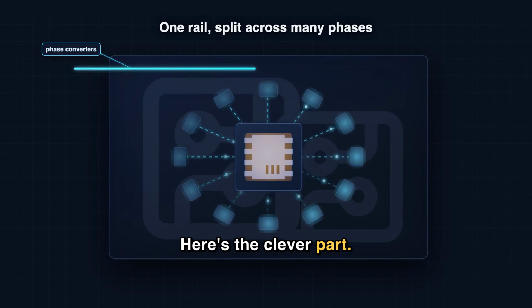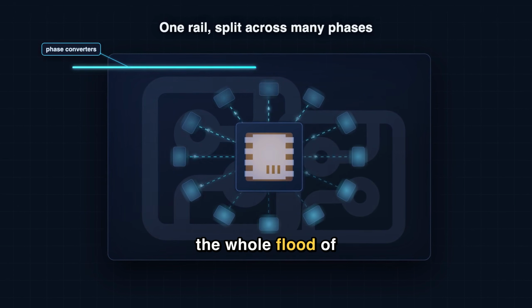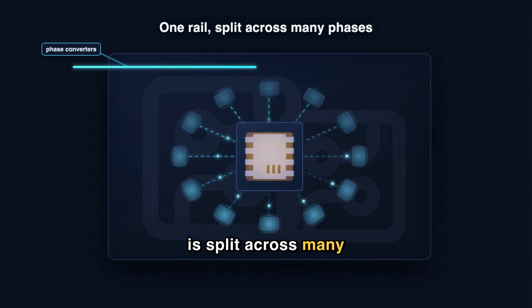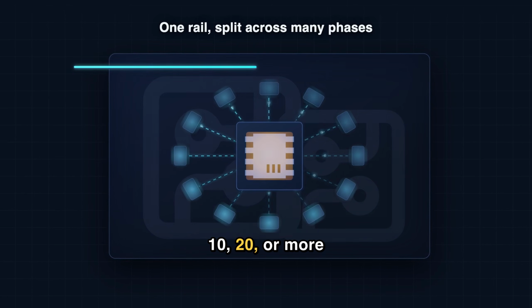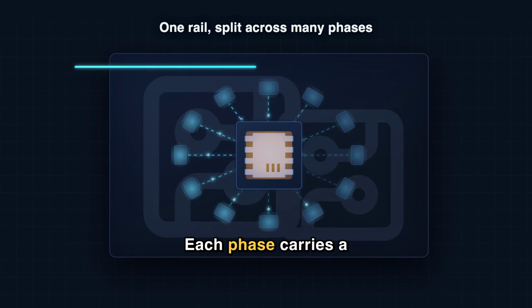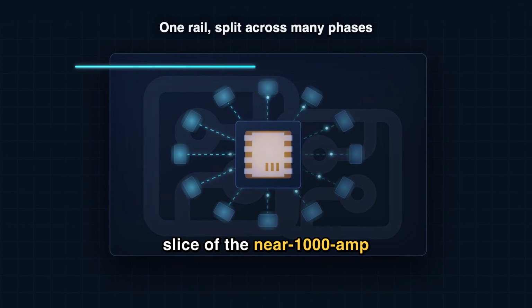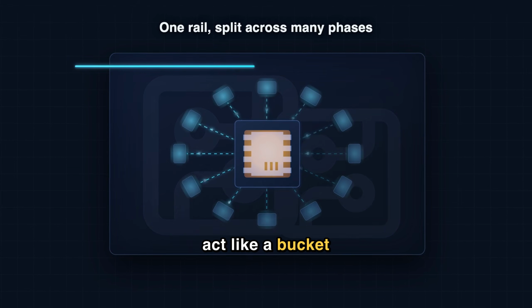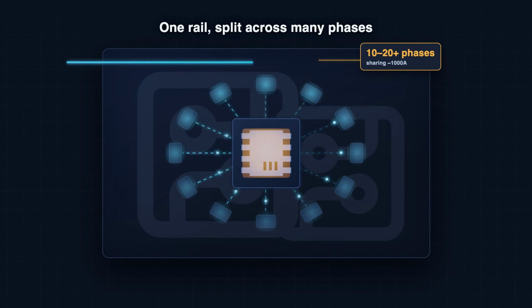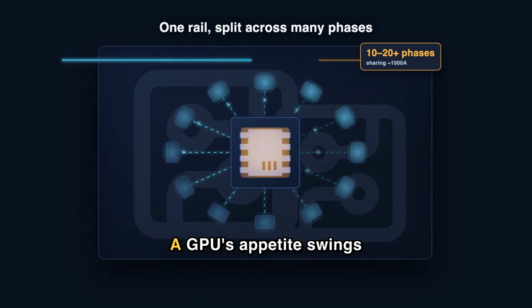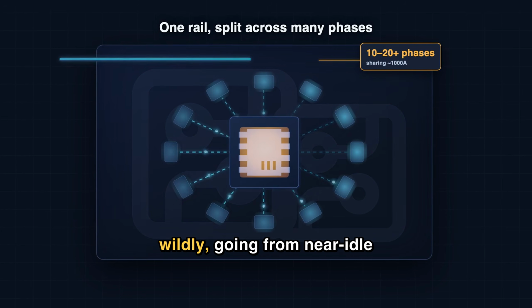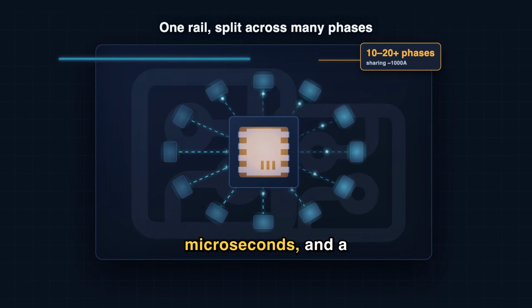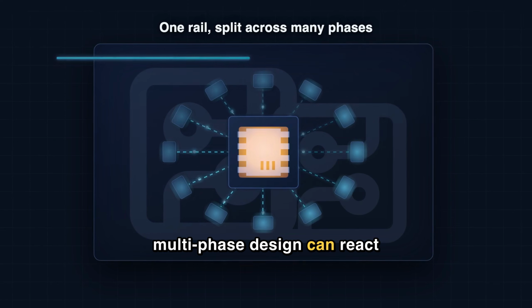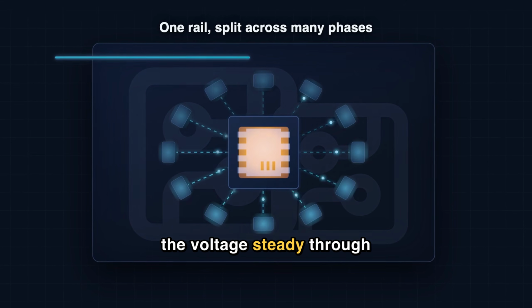Here's the clever part. One converter can't handle the whole flood of current, so the job is split across many working in parallel, often 10, 20, or more of these phases. Each phase carries a slice of the near 1,000 amp load, and together they act like a bucket brigade handing current to the die. Splitting the work does something else too. A GPU's appetite swings wildly, going from near idle to full throttle in microseconds, and a multi-phase design can react fast enough to hold the voltage steady through those swings.